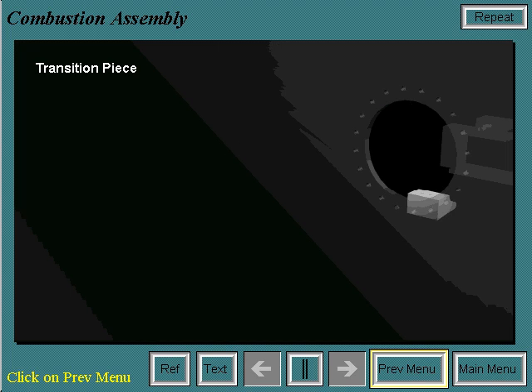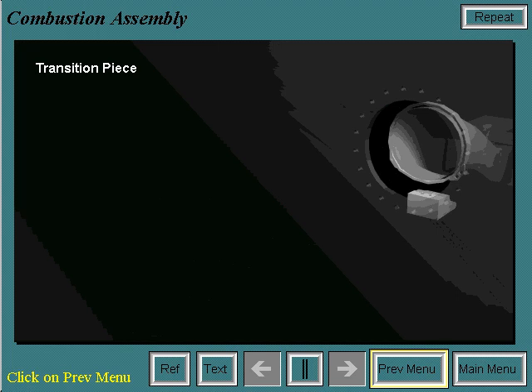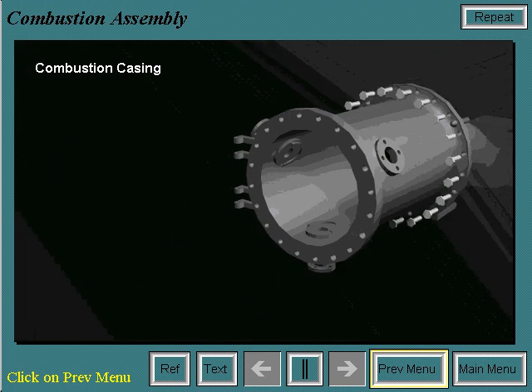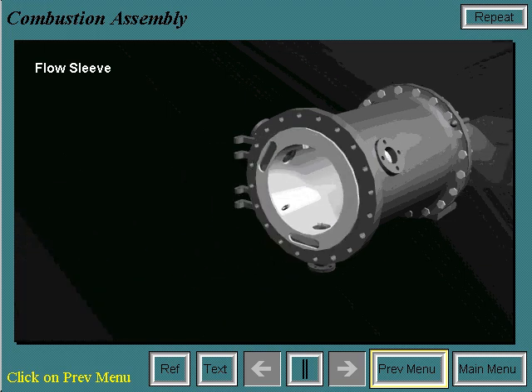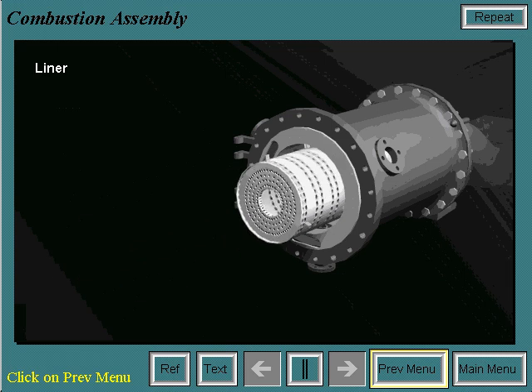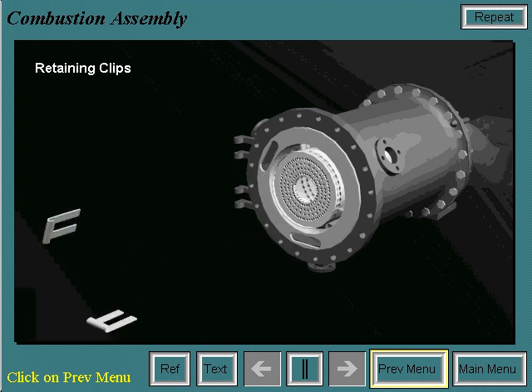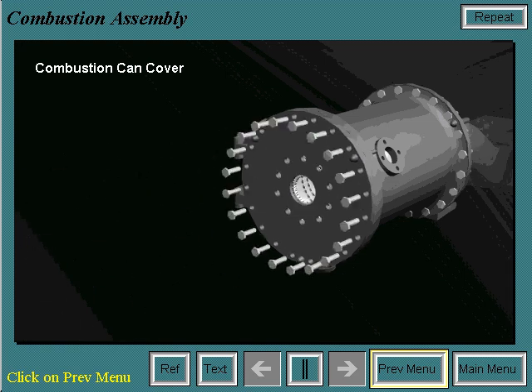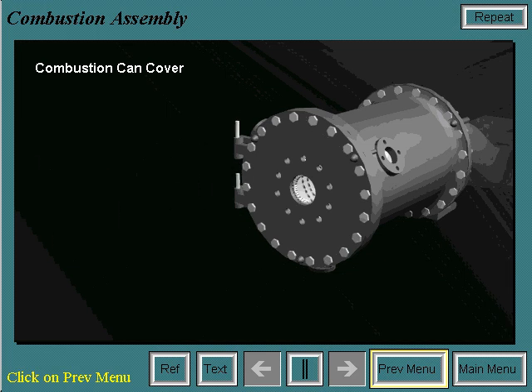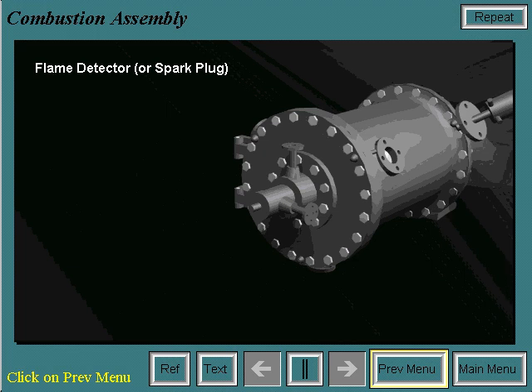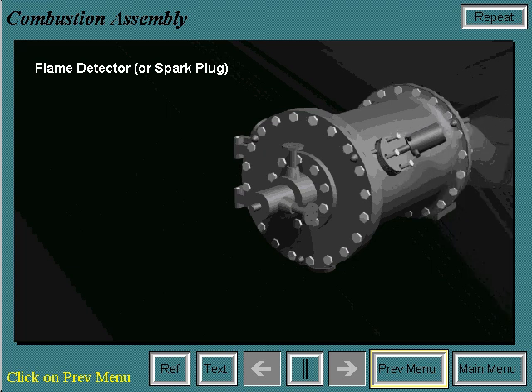The assembly of the combustion system begins with the transition piece bolted to the first stage nozzle on its aft end and supported by the bullhorn bracket on its forward end. Next, the combustion casing is bolted onto the combustion wrapper. Then the flow sleeve slides into the casing. The crossfire tubes are then installed but pushed out of the way so that the liner may be installed. Once it is, the crossfire tubes are put into the crossfire tube collars in the liner. Retaining clips keep the crossfire tubes in place. Next, the combustion can cover is bolted onto the combustion casing, and then the fuel nozzle is installed onto the combustion can cover. Spark plugs and flame detectors are also installed on certain combustion cans depending on the vintage of the unit.